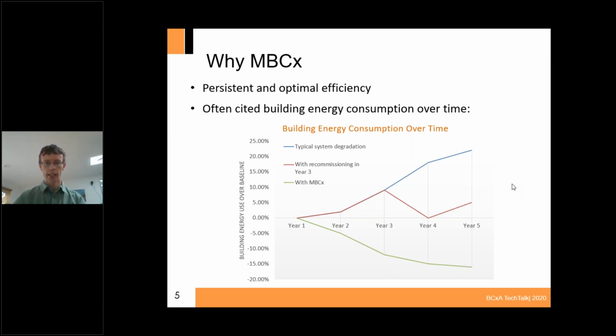So we can fine-tune the building to really meet what the owners and occupants need. Let's say, for example, you initially put in schedules of 5 a.m. to 7 p.m., and you realize people are coming in over the weekends as well, or now you know the occupants aren't there for that kind of time—you can start pulling back on that. You can modify the schedule and the set points too, fine-tuning your DP set points, static pressure set points, and temperature and humidity set points to really meet the owners' and occupants' needs.